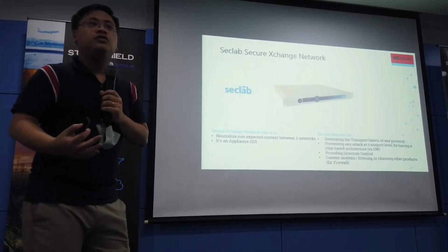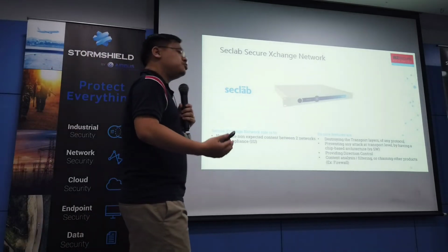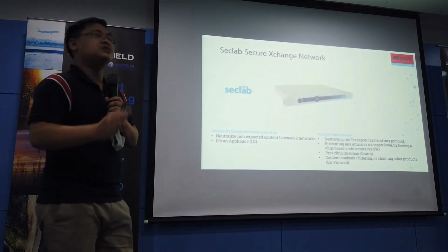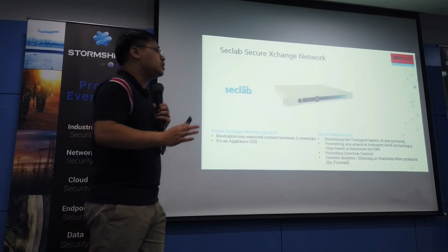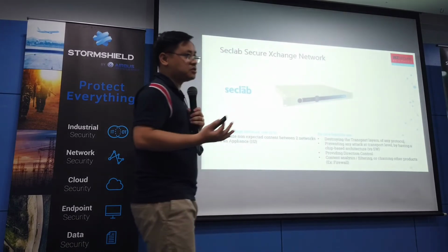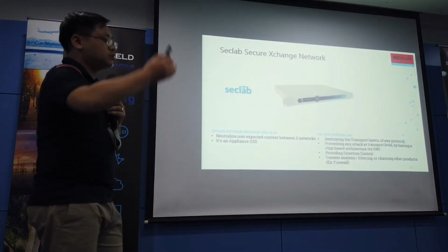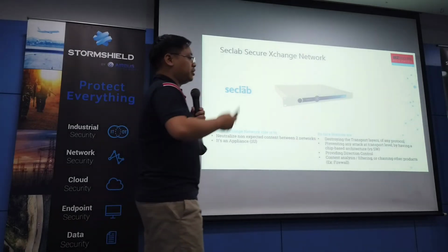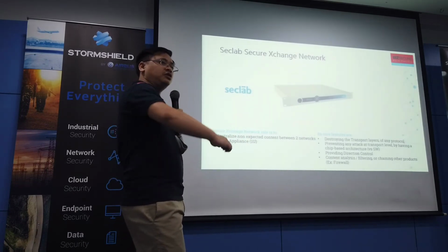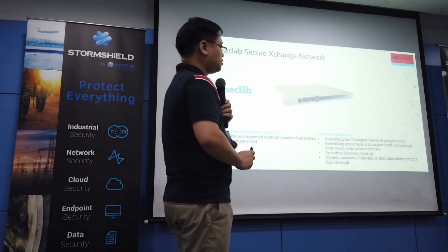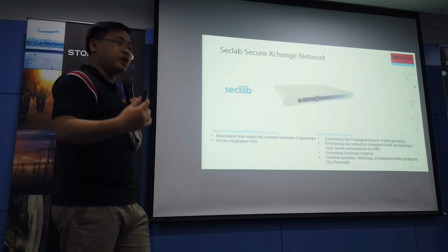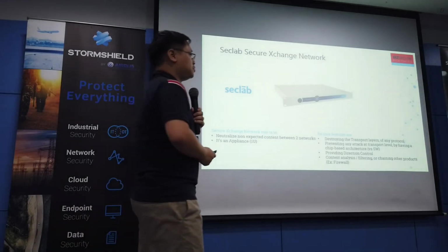So usually, if you've been working in OT for a long time, the equivalent would be, for example, a data diode. It's not the same technology, but in the end, you have this kind of thing. But again, it's not the same technology as a data diode. Okay. So as a reminder, what is a data diode? A data diode allows you to send traffic only in one direction, and you cannot receive any traffic back. Only in one direction. Here again, it's completely different. SecLab will allow you to have traffic in both directions, depending on the security policy that you have chosen.